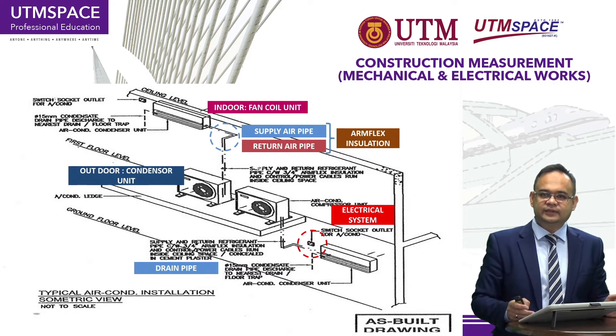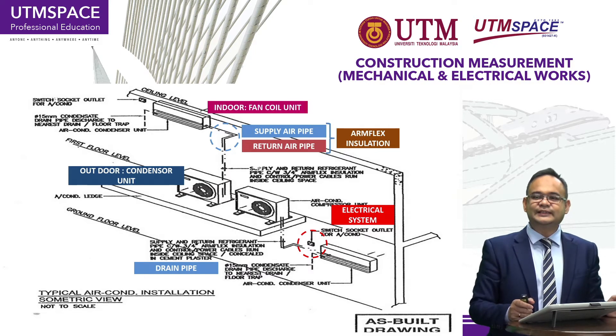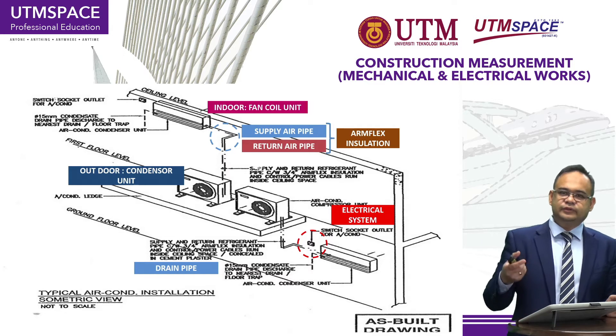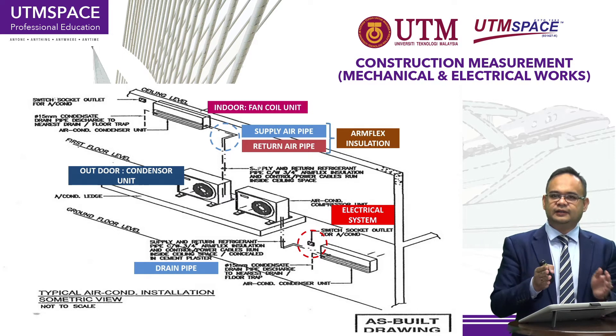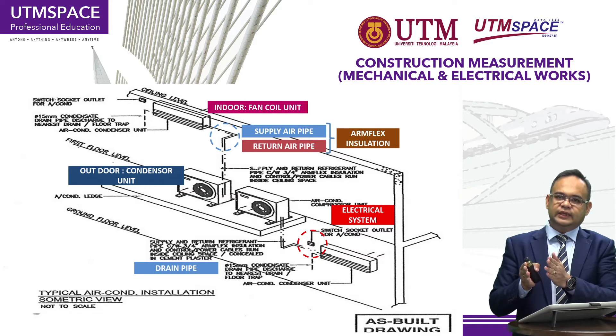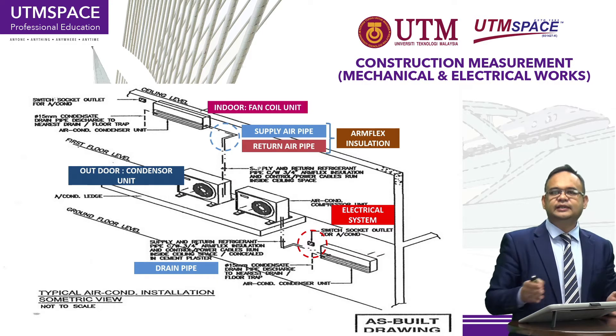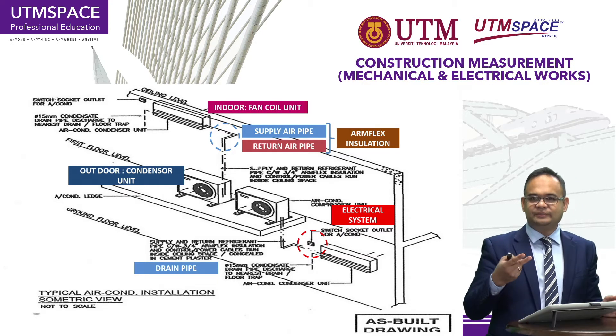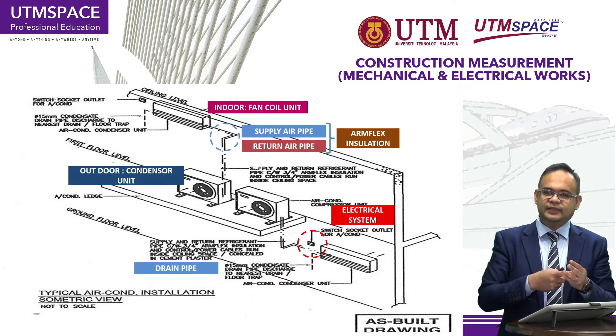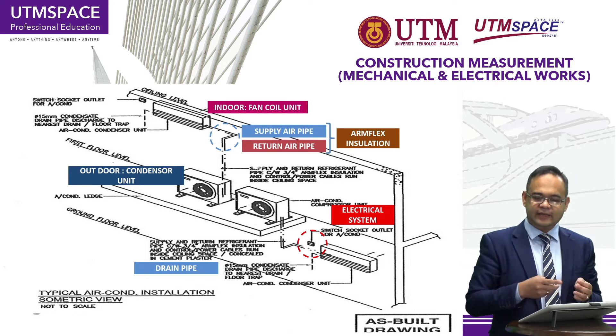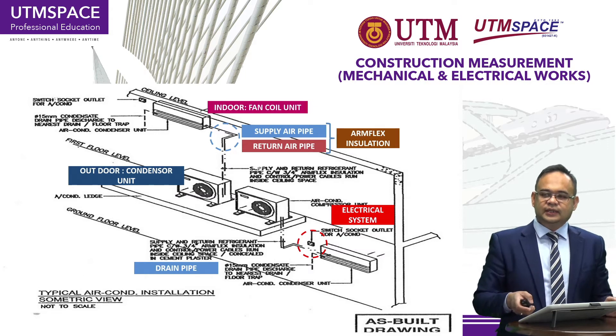Another pipe is what we call the condensate pipe, which normally uses PVC pipe. From the FCU we channel the condensate water to the nearest drain. There are three types of pipes for air conditioning installation: supply pipe, return pipe, and condensate pipe. The supply pipe requires insulation.